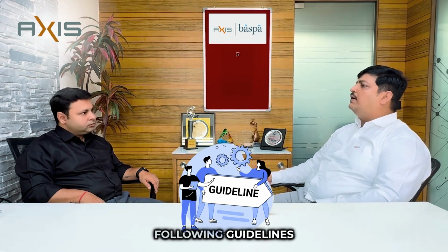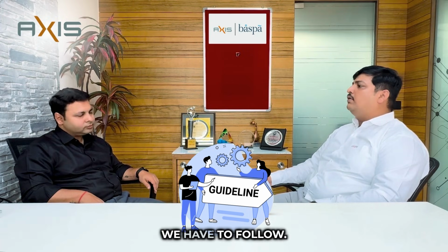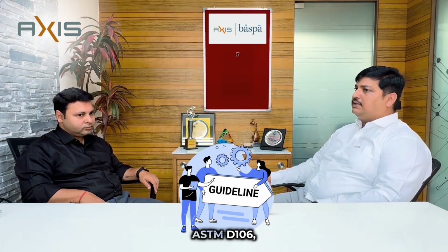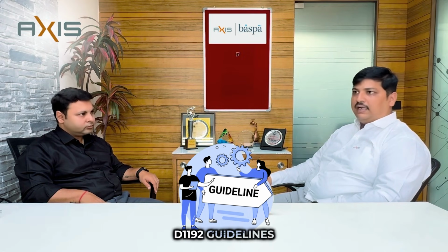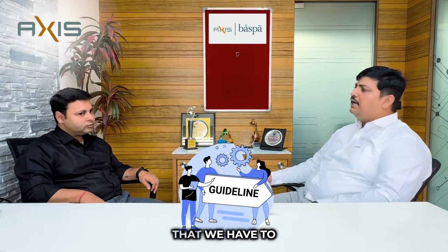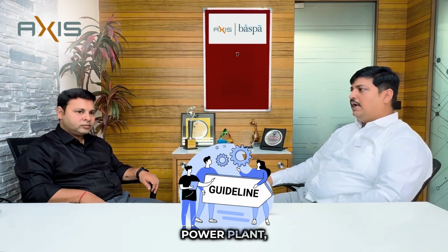And there are some guidelines that we compulsorily have to follow. There are power plant ASTM guidelines, yes, ASTM D1066, D1192. There are EPRI guidelines and IS Indian Standard guidelines that we have to follow for each power plant, and they must install the SWAS system.